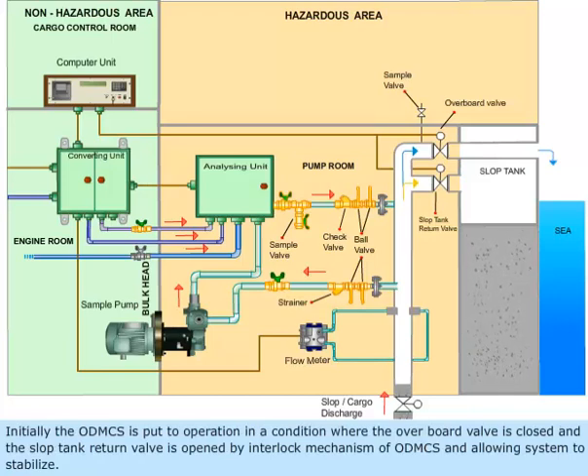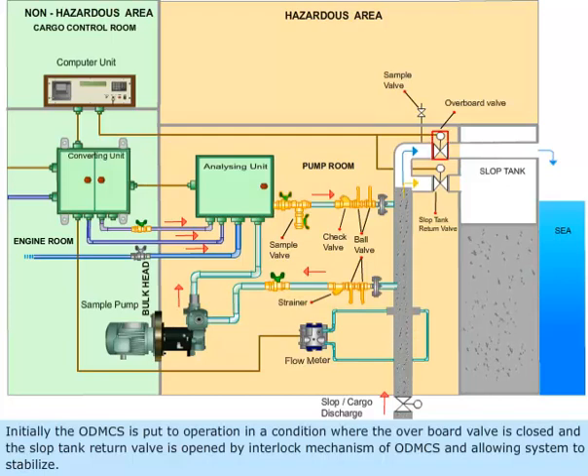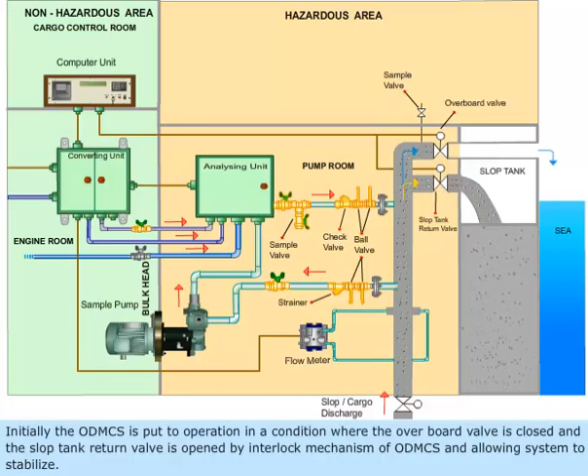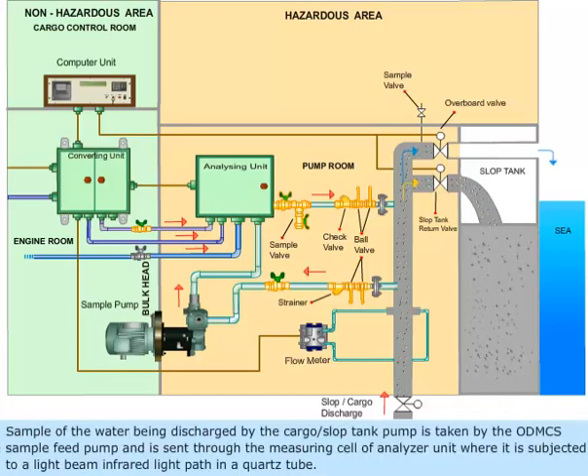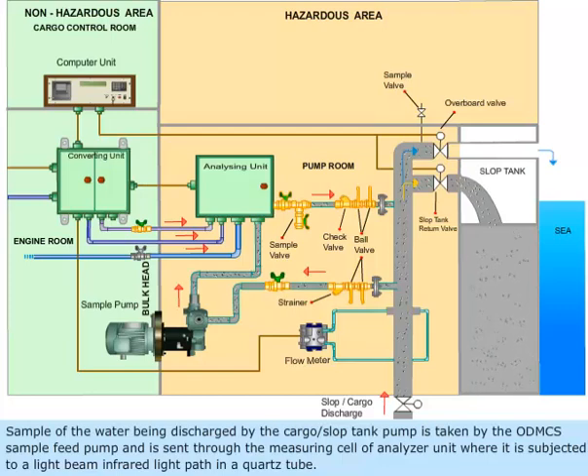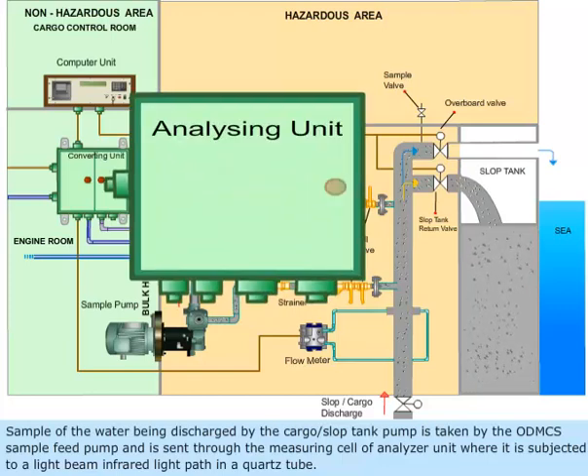Initially, the ODMCS is put to operation in a condition where the overboard valve is closed and the slop tank return valve is opened by the interlock mechanism of ODMCS, allowing the system to stabilize. A sample of the water being discharged by the cargo or slop tank pump is taken by the ODMCS sample feed pump and sent through the measuring cell of the analyzer unit.